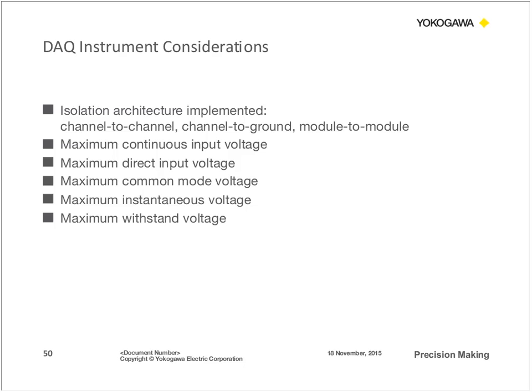Maximum instantaneous voltage is for the case where you're dealing with very high transient voltages. So if you run the risk of lightning strikes, you want to make sure that the specification will run into hundreds of thousands of volts to protect your instrument and your user. And last one, the maximum withstand voltage. This is the maximum voltage that the insulation material can handle before the barrier starts to break down. So typically the isolation barrier is some sort of insulation material. If you apply too much voltage, that can start to affect the performance of the insulation as well.